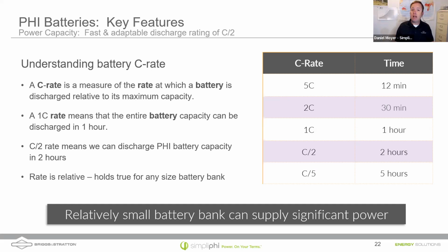Maybe you don't have a generator and you have solar with a small solar window to charge the batteries—you can still charge that battery up quickly. It also means that if you come out and do a lead acid battery replacement, those lead acid batteries typically have more of a C/20 or C/10 discharge rate, or C/5 if you're really hammering on them. You don't need as many batteries in the bank to handle that power requirement.